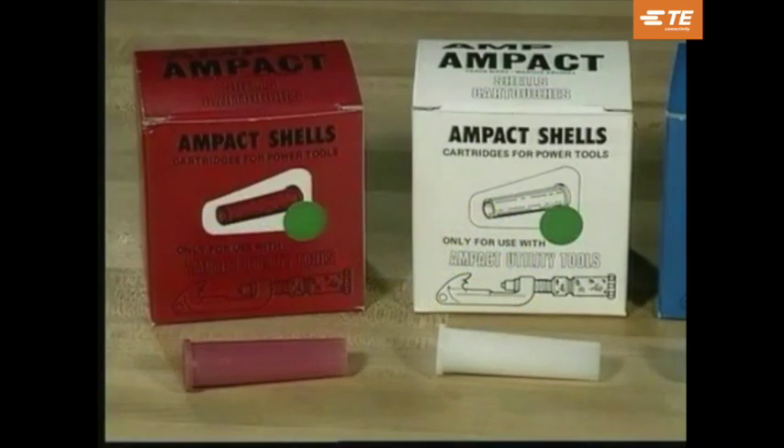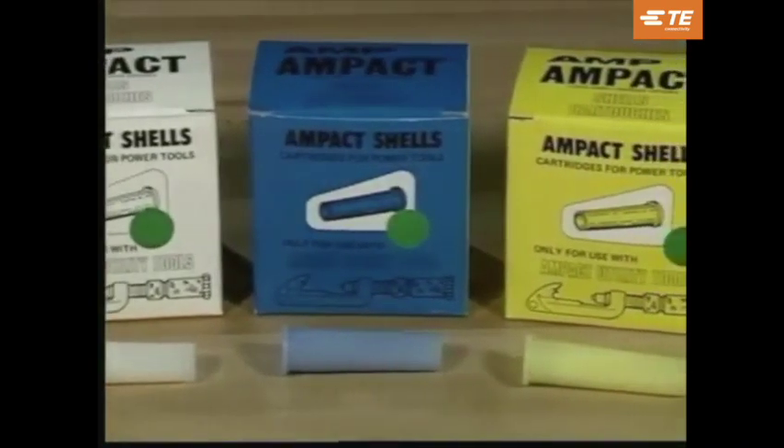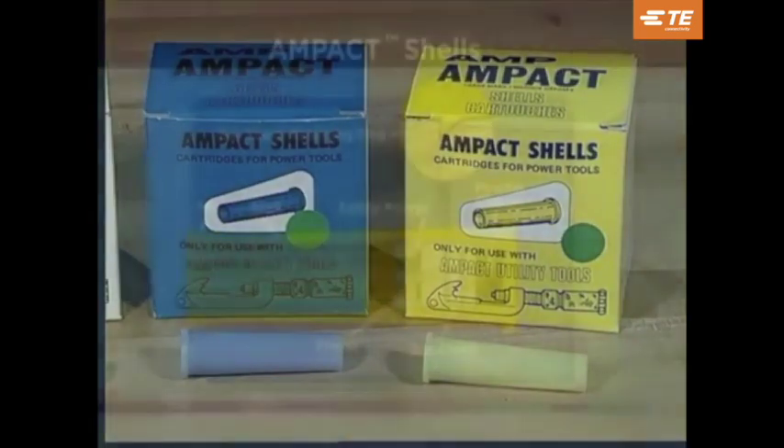The AMPACT tap system uses four color-coded shells, each containing a different powder charge. The red, or smaller shell, is used to apply red-coated taps and is used to remove red, white, and blue-coated taps. The white shell is used to apply type 2 and copper taps, but should not be used for removal. The blue or medium shell is used to apply blue-coated taps and also to remove yellow-coated taps. The largest shell is color-coded yellow and is used to apply yellow-coated taps. Yellow shells should never be used for removal.